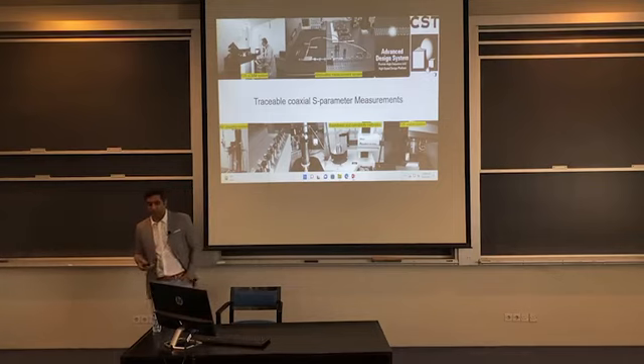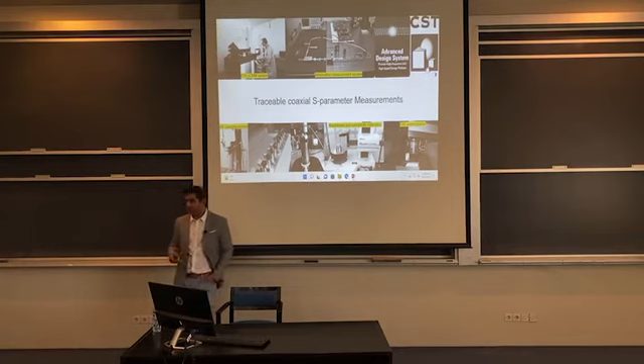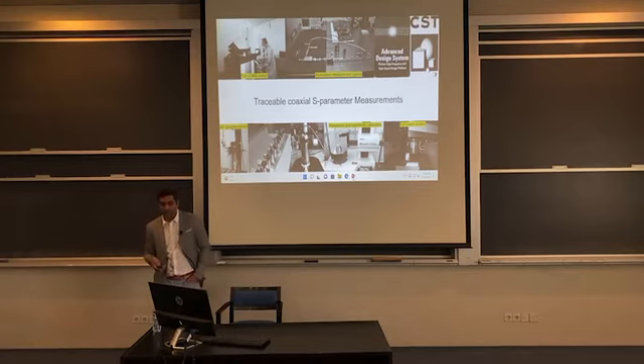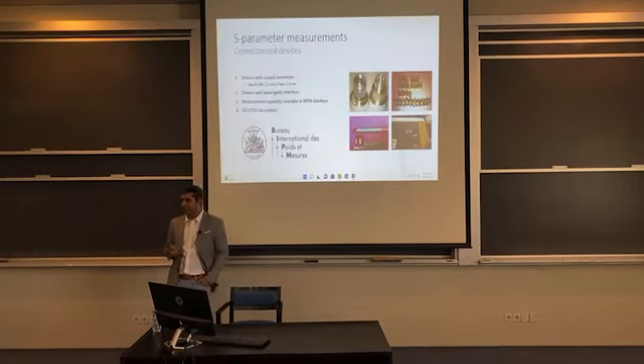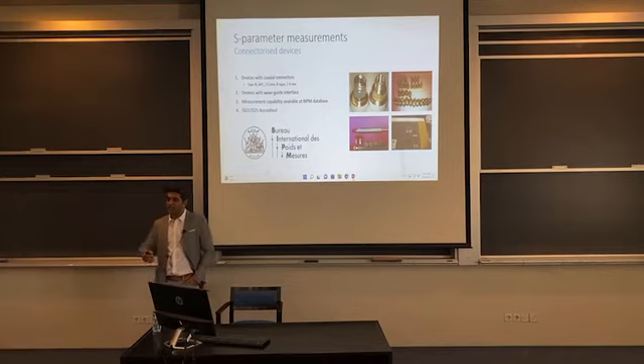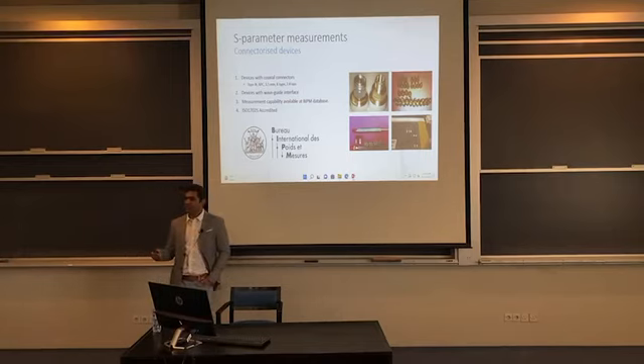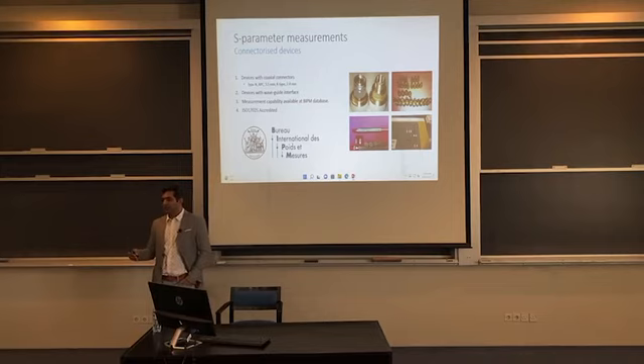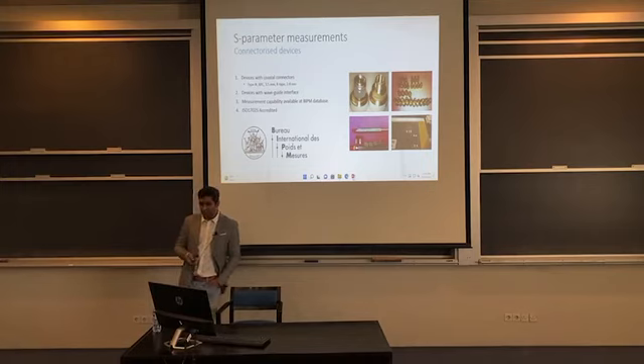The first measurement capability our group developed was for connectorized devices, because these are needed to calibrate your equipment in the first place. When you buy a VNA, you buy a calibration kit for it, and that calibration kit needs to be calibrated by an NMI like us. So how do we develop a measurement facility for calibration of such devices?